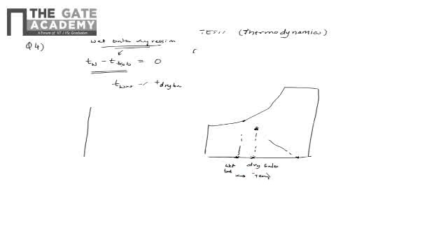has to be 0. Obviously your point of concern has to be here. If your point of concern is here, the wet bulb and the dry bulb are same. Otherwise, if it is anywhere inside, the wet bulb is, when you just draw this inclined line, these inclined lines are the lines of constant wet bulb. So when you take this till this inclined curve, which is of 100 relative humidity, till this point you take, and then if you look at the wet bulb temperature, so when you look at the temperature, that is the wet bulb.